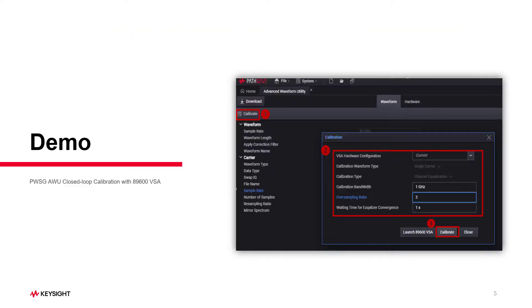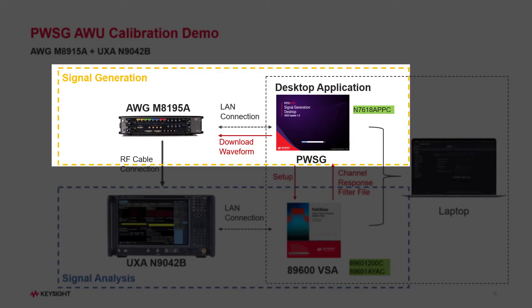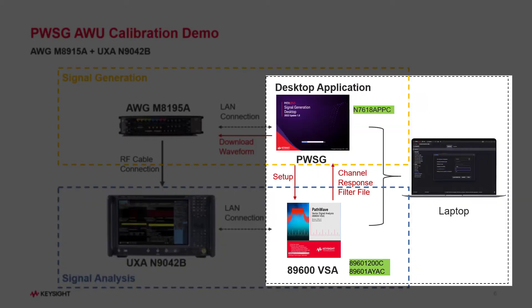Let's see a demo of how to use this PWSG AWU closed-loop calibration with VSA. Before we start the demo, we need to set up the calibration system. There are three main parts: the yellow area is for signal generation, the blue area is for signal analysis, and the black area is for the desktop software on the PC.